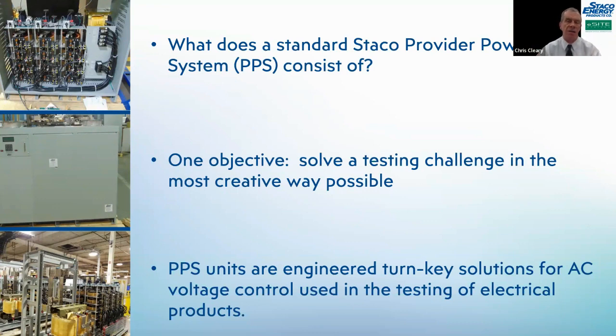So we can custom specify where the tap could be. We could get a 120% boost. However, you lose the current rating. As you go up in your boost and change this very specific location of where a tap is on the variable transformer, you lose your current rating. So a little bit here and there, you might have to add more variable transformers, increasing the cost of the system. So you've got to balance that economics with the design of the system.